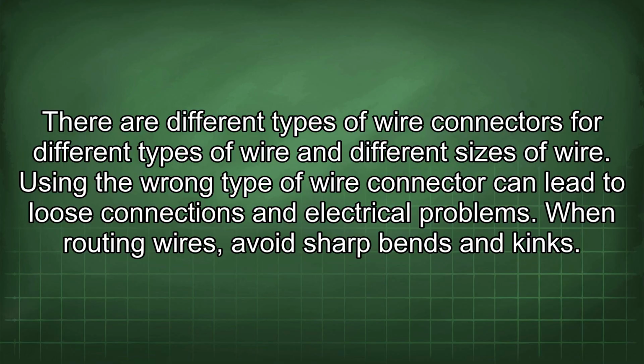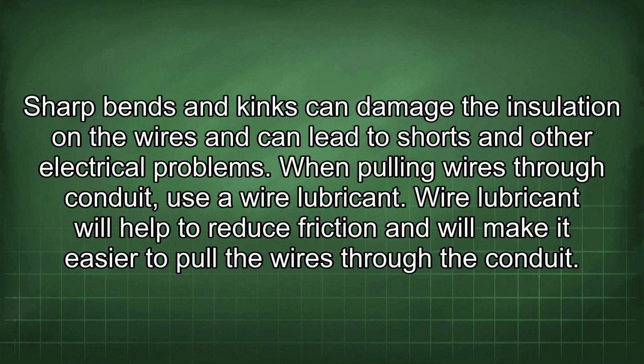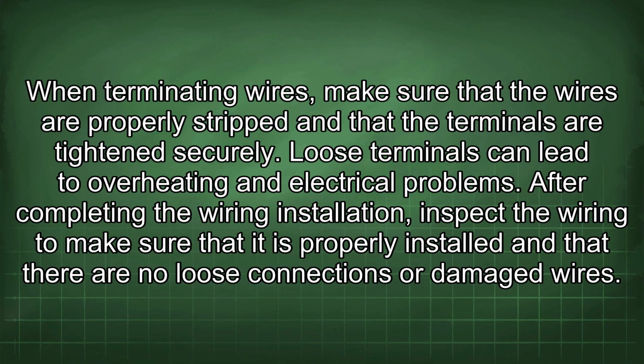When routing wires, avoid sharp bends and kinks. Sharp bends and kinks can damage the insulation on the wires and can lead to shorts and other electrical problems. When pulling wires through conduit, use a wire lubricant. Wire lubricant will help to reduce friction and will make it easier to pull the wires through the conduit. When terminating wires, make sure that the wires are properly stripped and that the terminals are tightened securely. Loose terminals can lead to overheating and electrical problems.